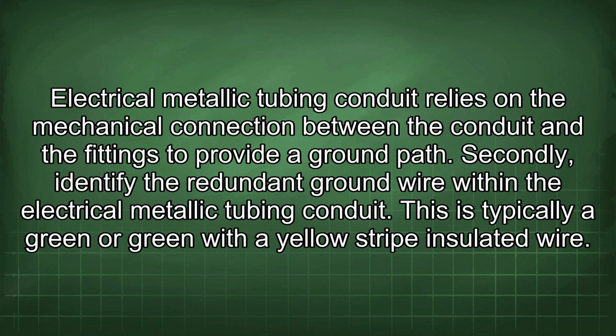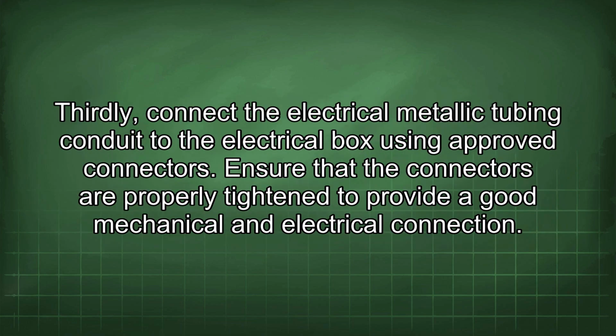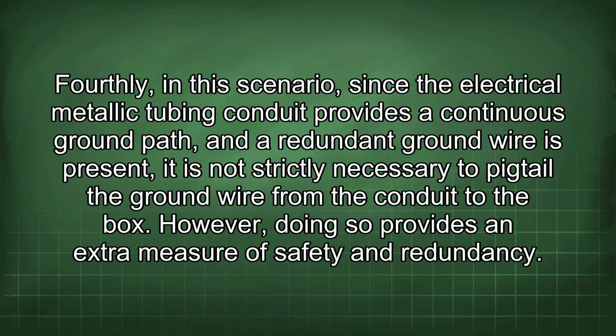Secondly, identify the redundant ground wire within the electrical metallic tubing conduit. This is typically a green or green with a yellow stripe insulated wire. Thirdly, connect the electrical metallic tubing conduit to the electrical box using approved connectors. Ensure that the connectors are properly tightened to provide a good mechanical and electrical connection. Fourthly, in this scenario, since the electrical metallic tubing conduit provides a continuous ground path, and a redundant ground wire is present, it is not strictly necessary to pigtail the ground wire from the conduit to the box.